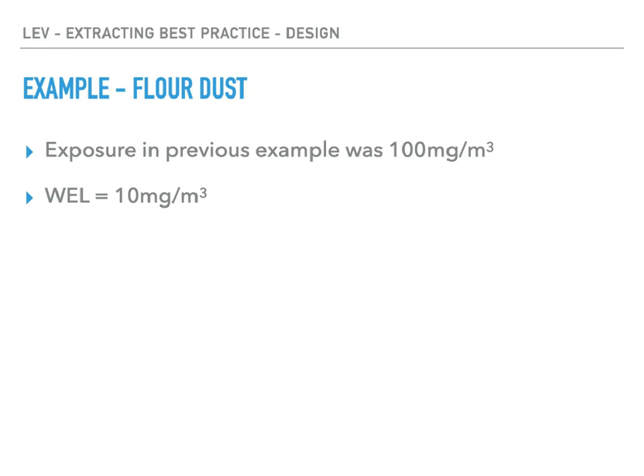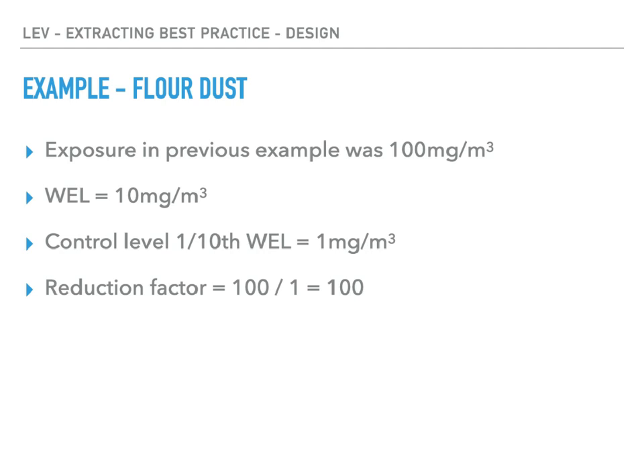So when we look at our flour dust example, the lady in the photo was exposed to 100 milligrams per cubic meter. The WEL is just 10 milligrams per cubic meter. We're going to control that to 1/10 because we don't know if she's average or not average, you know, there's no way of telling, it's all in their DNA makeup. So we have to protect as many people as we can, so we always move the line to the left to reduce the exposure down, and we work on a factor of 1/10. That's quite common in the LEV industry. So that gives a reduction factor from 100 milligrams per meter cubed in the air down to an exposure level of 1 milligram. So we're looking for a reduction factor from our LEV system of 100.